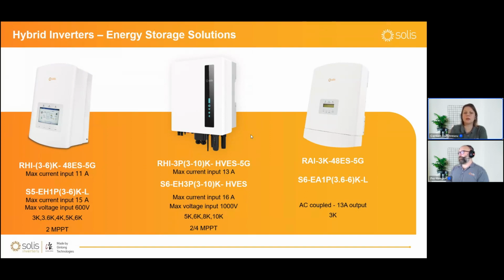So it's a single phase inverter, which will allow every customer who already has a PV inverter string, grid-tied inverter, but without batteries, if they want to add storage capabilities to their existing PV systems, they don't have to change their equipment altogether. They can just have the RAI with a battery connected. This RAI will connect to the AC side, and it will collect the excess of energy that is not being consumed locally, and it will capture that energy and store it in the batteries, and it can be used later when it's needed. For example, when there is no PV anymore.